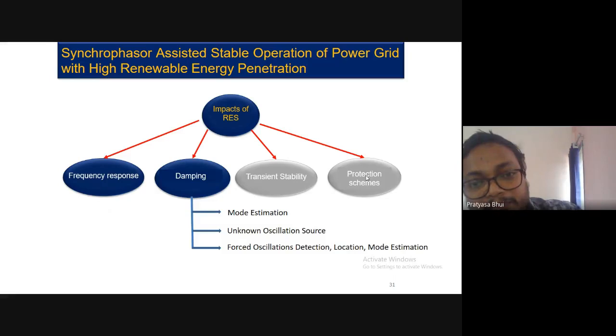Then you have damping or the small signal stability. So you can estimate the modes. Oscillation frequency estimation is also a very important topic, because even without any disturbance, there are continuous small disturbances in terms of generation and loads. Your loads are always fluctuating and your generation is also always changing. Because of this ambient fluctuation, you get oscillations in the line power flows and the frequency. These are called ambient oscillations, and in these ambient measurements you can find the mode, frequency, and the damping.